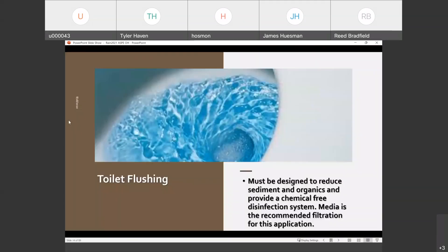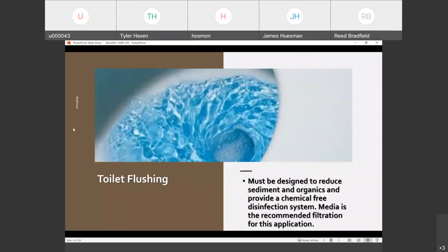Toilet flushing is sort of the second tier. We're bringing water inside the building, so we want to design it carefully — sediment control is big; we don't want to be clogging up anybody's flush valves. We want to make sure we have good disinfection. In some instances, the authority having jurisdiction will tell us we have to color that water. We use a blue dye — it's pretty standard in the industry and differentiates between the non-potable and the potable water. There is some media filtration in there to get down to those micron levels we need.